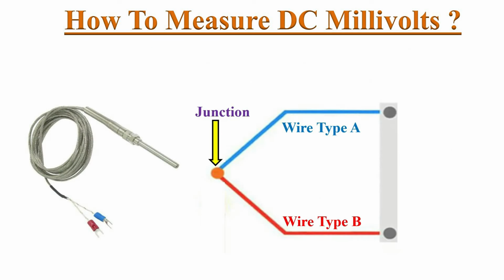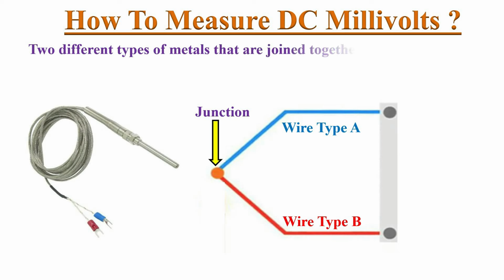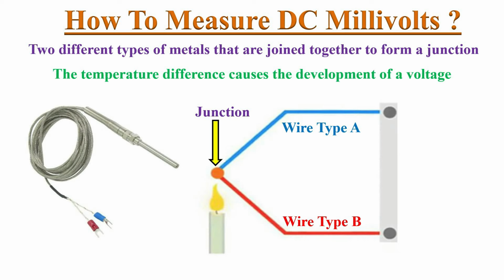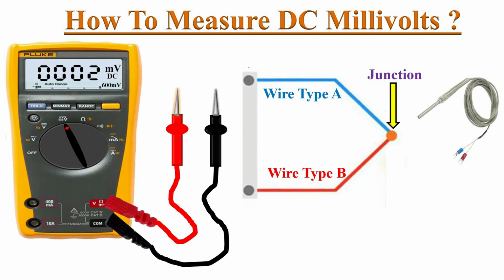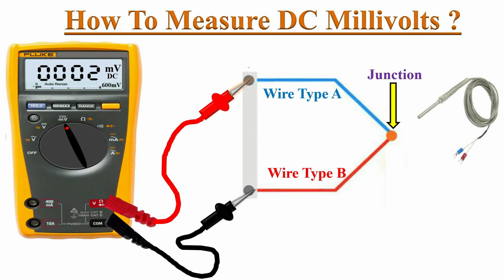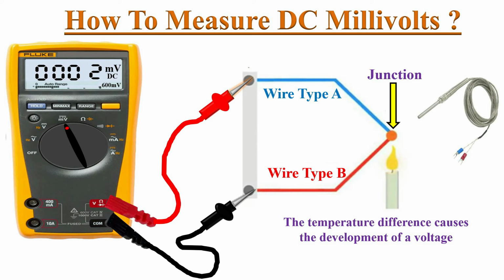A thermocouple is a temperature sensor used to figure out how hot or cold something is. It consists of two dissimilar metal wires that are joined together to form a junction. When the temperature at this junction changes, a small measurable voltage is generated at the other ends of the wires. The amount of voltage produced depends on the temperature at the junction. We can measure this small voltage with the DC millivolts function in the multimeter. Just connect the test probes of the meter to the two ends of the thermocouple and ignite a candle or other heat source at the junction. A good thermocouple produces 25 to 30 millivolts. The multimeter shows this millivolts reading on its display.